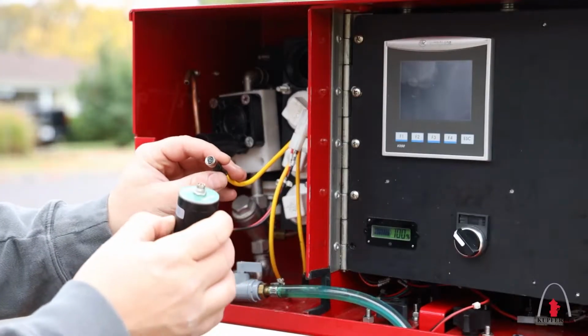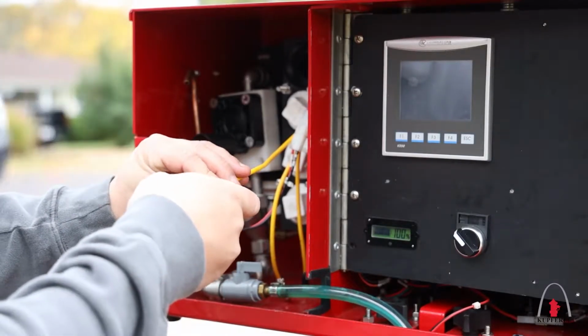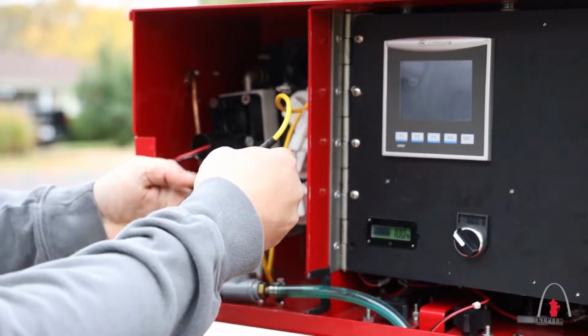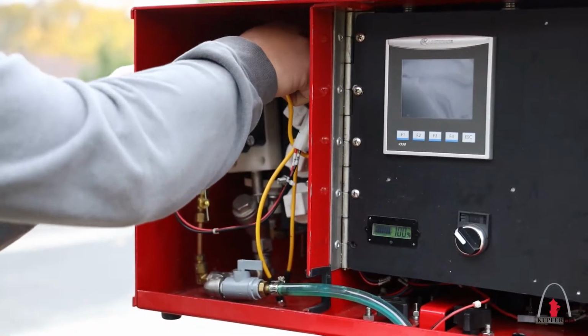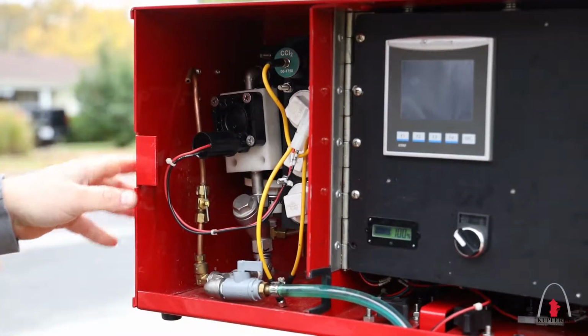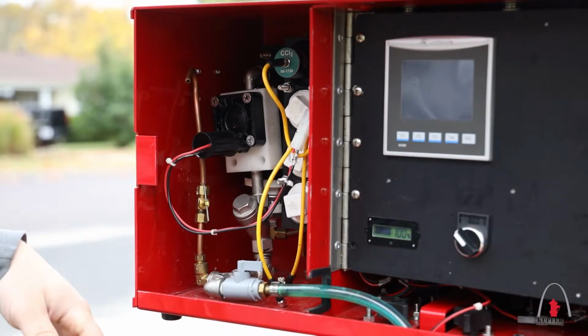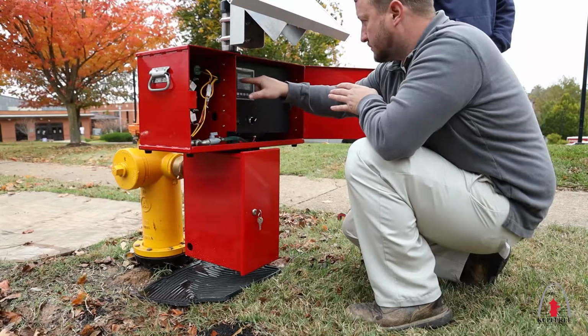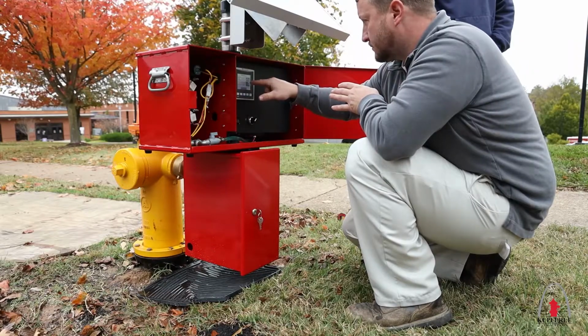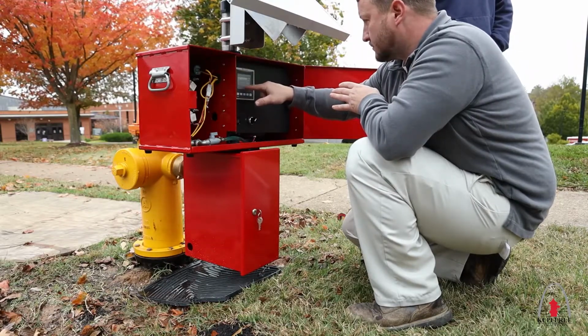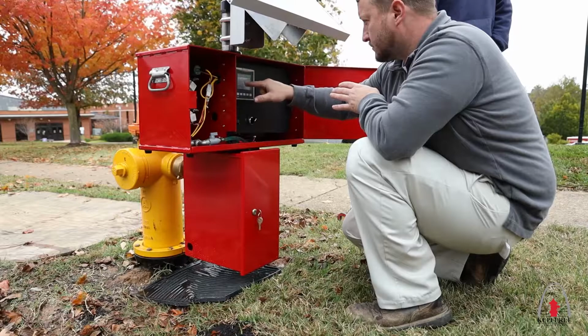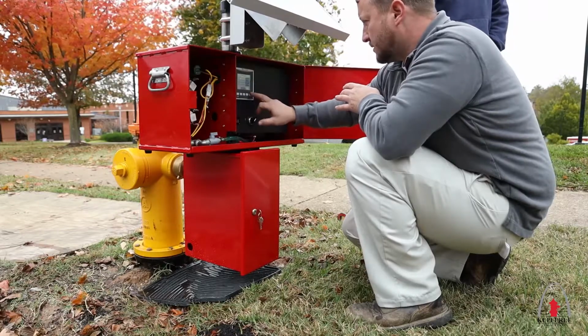If not already installed, plug in the chlorine sensor and/or other sensors into the unit by plugging into the flow cell bank, making the electrical connection with the yellow cable and turning 90 degrees to secure. If the sensor hasn't been calibrated already, take a hand sample and calibrate the sensor on the PLC. Program the PLC's minimum residual level and desired residual level.